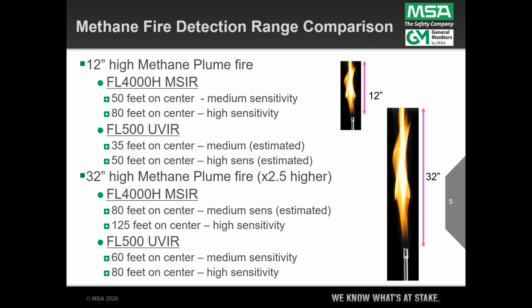So what it means is, and this is an option for every customer to consider, if I am going to expect a detection of a 12-inch high methane fire, then I'm going to get some detection range. And that's what I've got here. I just listed the MSIR detector first on both medium and high. And so to a 12-inch high plume fire, the MSIR can see that on the medium sensitivity of 50 feet on center, 80 feet on high sensitivity. And then our UVIR, 35 feet on center at medium and 50 feet on center on high sensitivity.